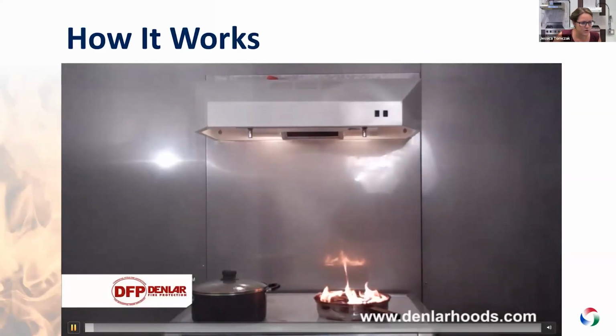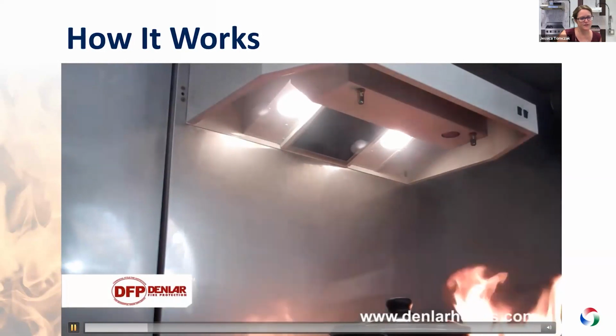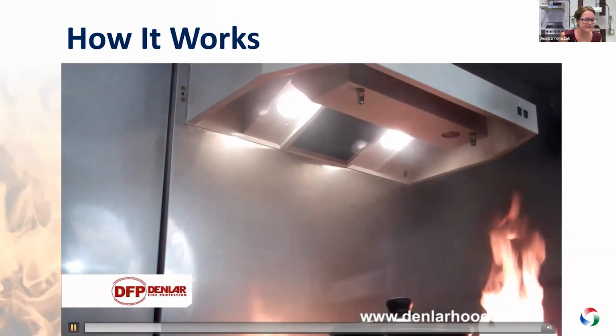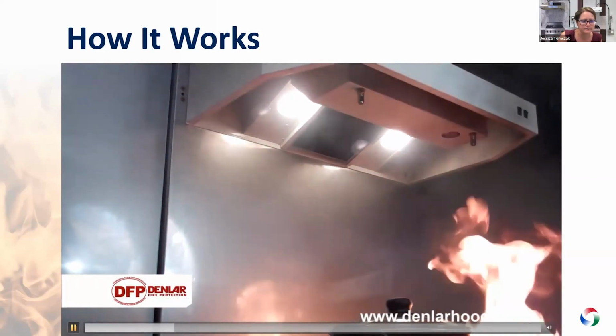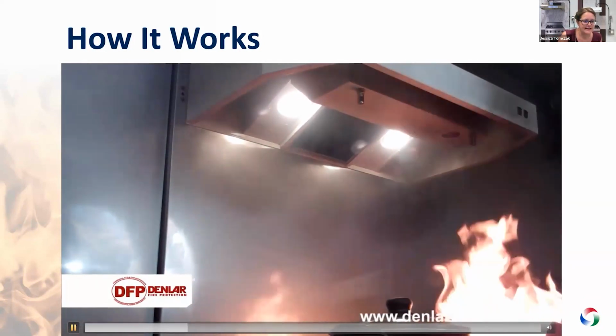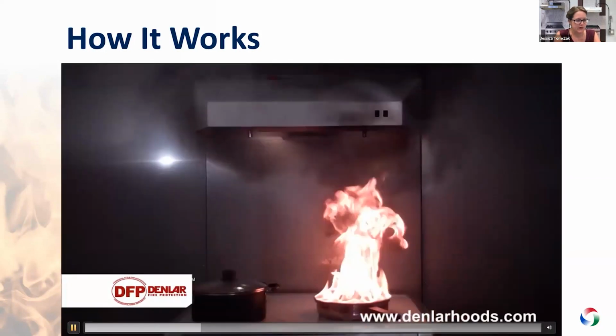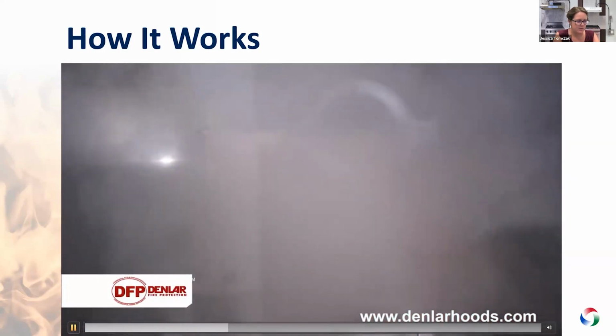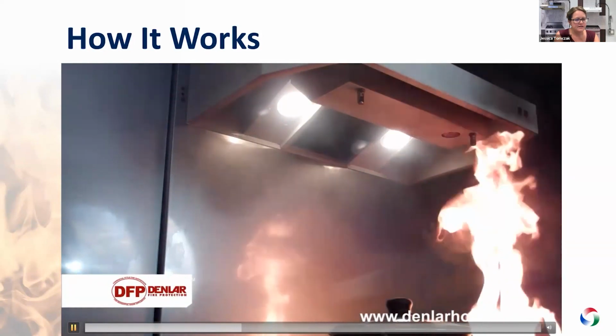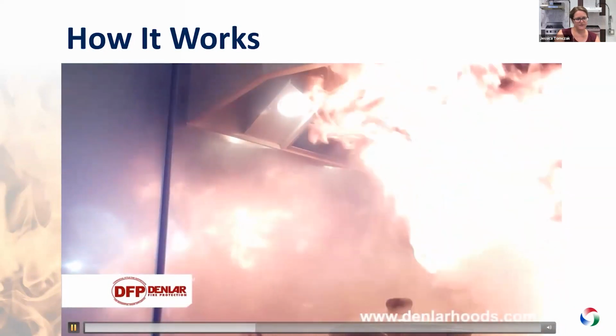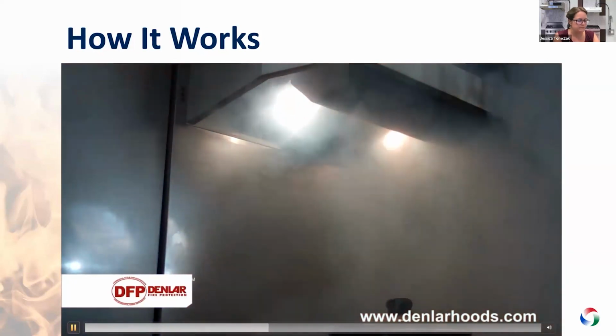And here we have a discharge video. So I'll kind of walk you through what's happening. But you're going to see in a second, the heat's going to flare. And as the heat continues to build, the temperature is going to increase at the links themselves. This is our designer series, for those of you wondering. And you're going to see in a second, the link assembly is going to break. And when that happens, you're going to see also the discharge nozzle caps are going to come off. And that suppression, you can see that spray gets wider the closer to the stove it gets, and that fire flares quickly and then it's put out.